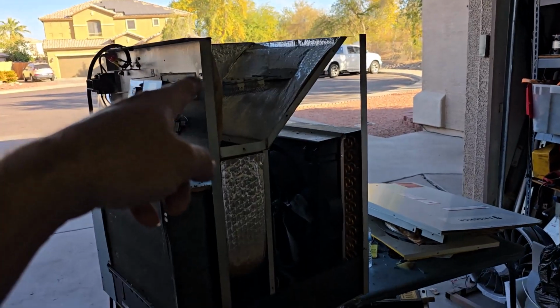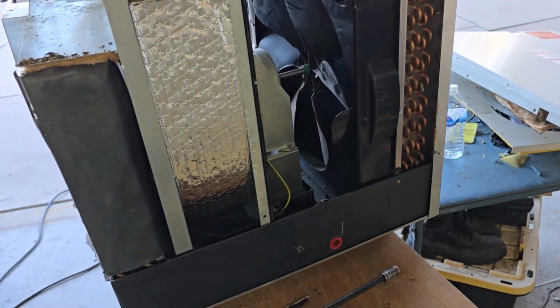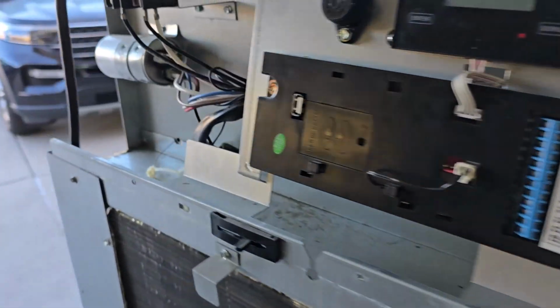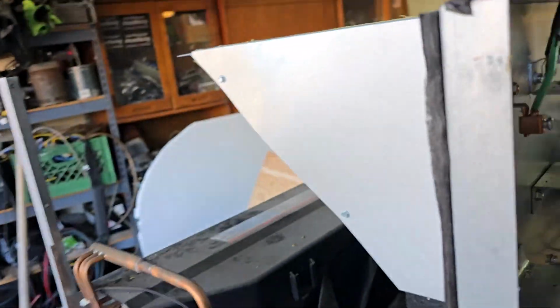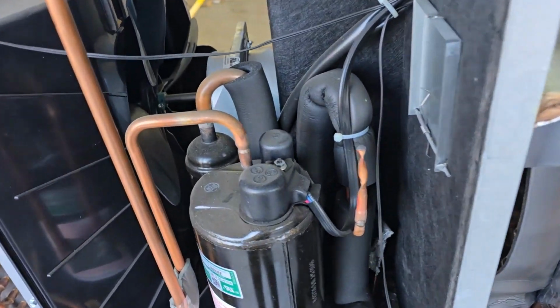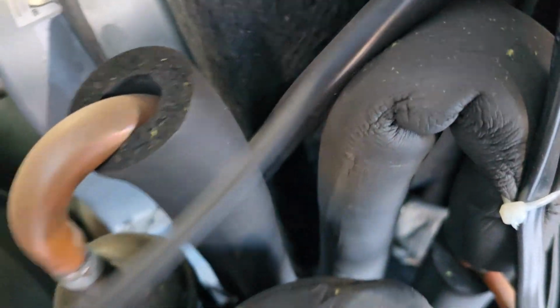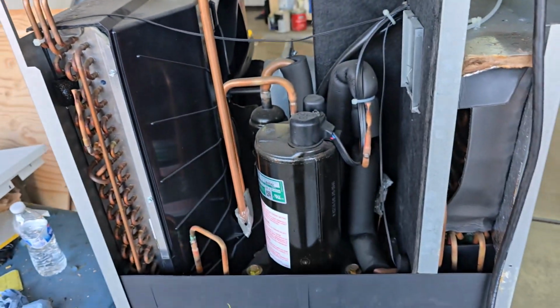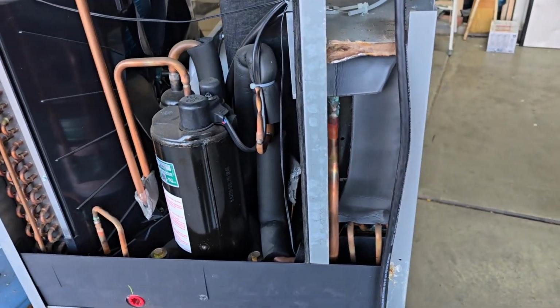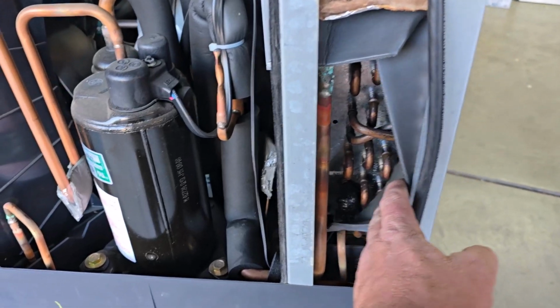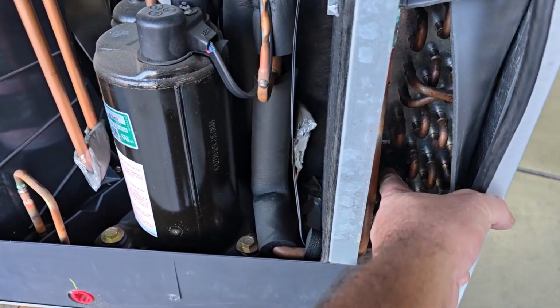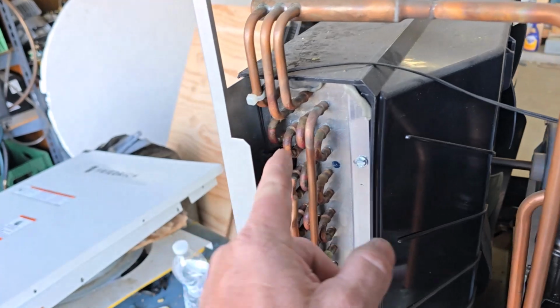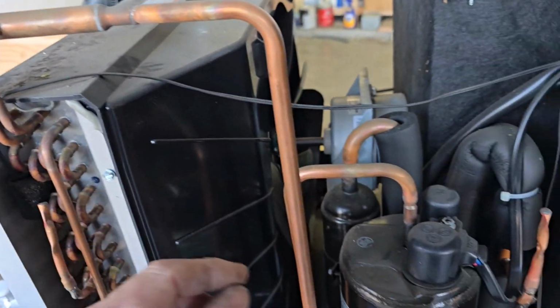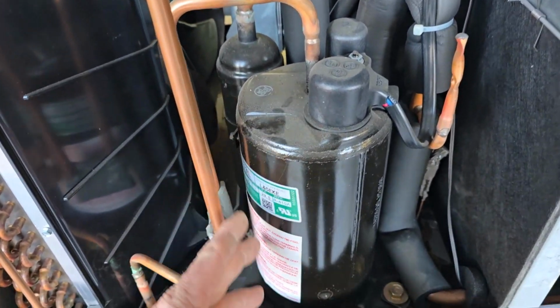Okay, got the top panel off and the side panel off. And this is funny - remember I was trying to get heat to work? Well, where's the reversing valve? It ain't got one, so evidently this model is a straight cool. So there's your indoor coil, it's got a sensor on it. Outdoor coil, it also has a sensor on it. Here's the compressor, which is a rotary.